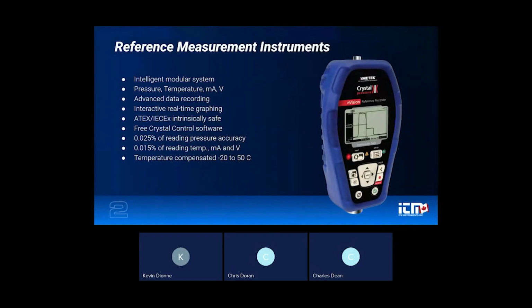So sometimes we want to look a little bit deeper into a system and have a little bit more measurement flexibility. And that's where these reference recorders come into play. The one that you're seeing on your screen there is the nVision by Crystal. At its foundation, it's not only a highly accurate reference standard for field calibration, but it's also your recorder. It can measure temperature, milliamps, and voltage. It's great for data recording, where your measurements can be logged automatically rather than written down or looked at after. You can see them in the moment. From an accuracy standpoint, it's extremely accurate, 0.025% of reading accuracy for pressure and 0.015% of reading accuracy for temperature, milliamps, and voltage. It's a great instrument when you need to look deeper into a system to do diagnostics, and another really good instrument that Crystal offers.